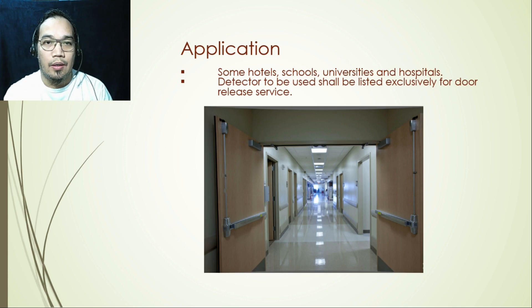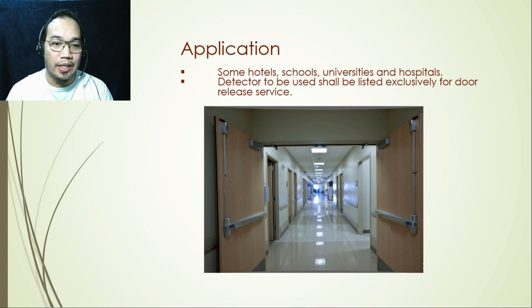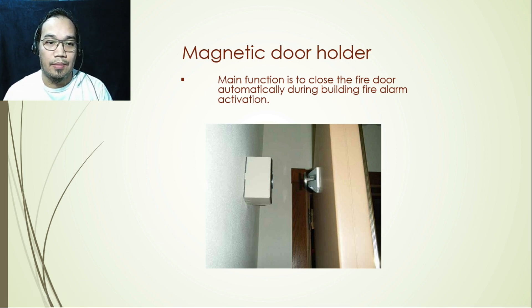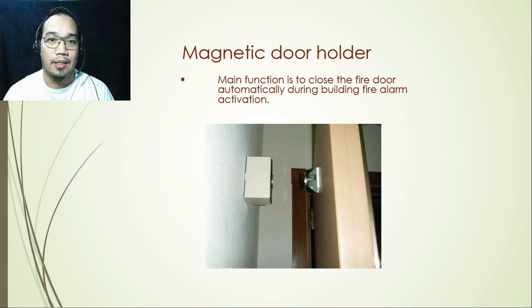So even if it's required to maintain this fire-rated door as closed, there is an exemption — like in a hospital. As you will see in this illustration, this door is held open, and at the back you can see where our magnetic door release is installed. This is how we maintain the door open during normal activity in the building. If we have this type of installation or fire door, it is required to have a smoke detector which activates the door to close in case of fire.